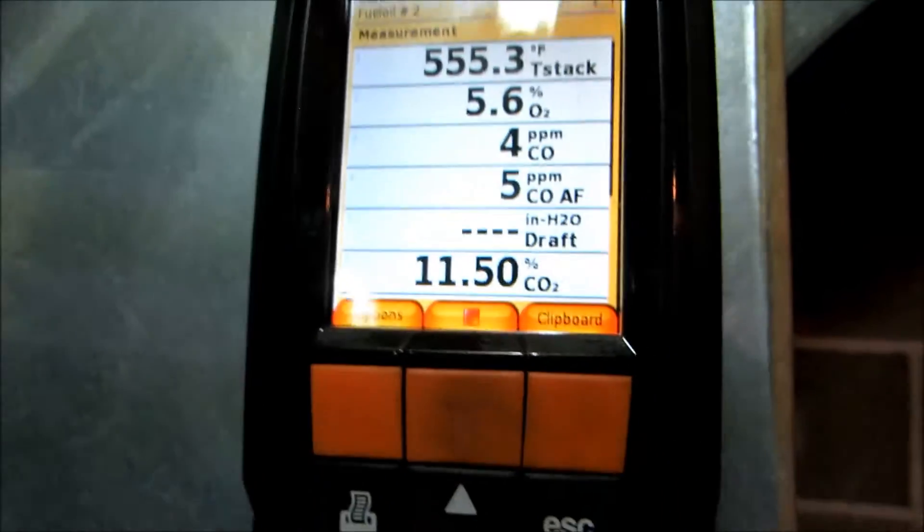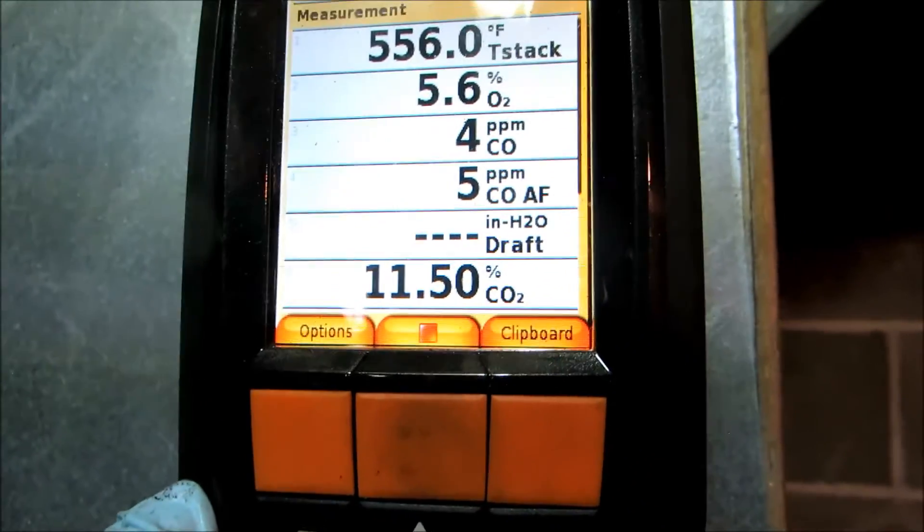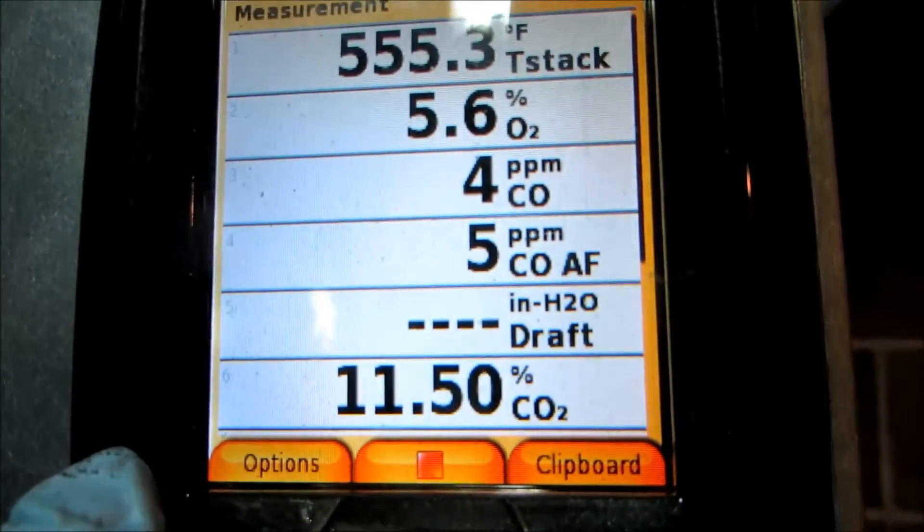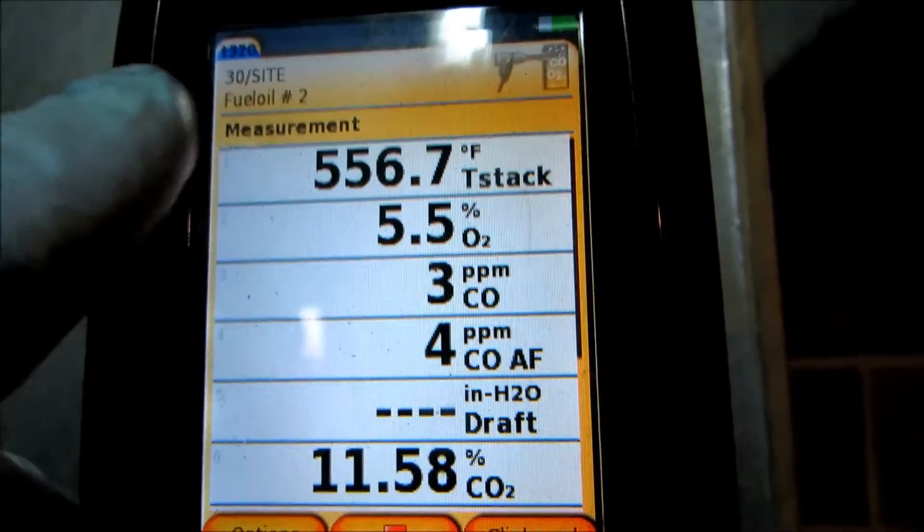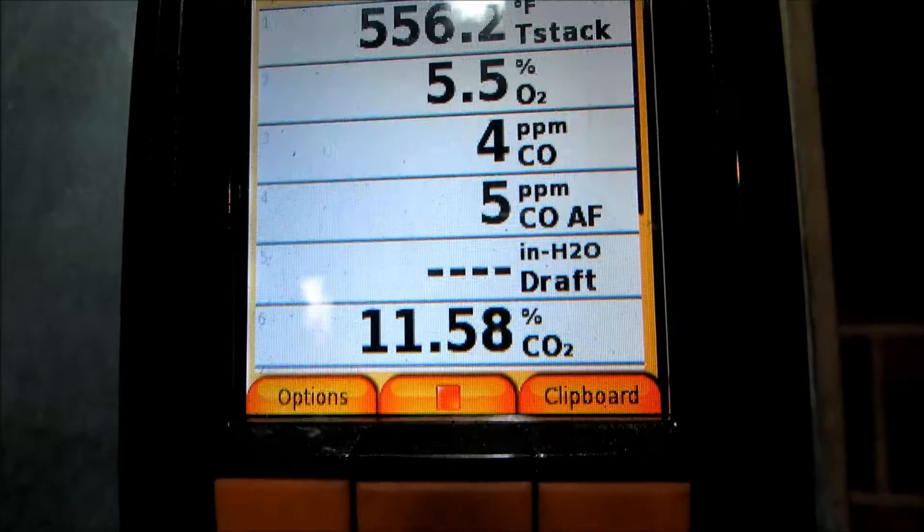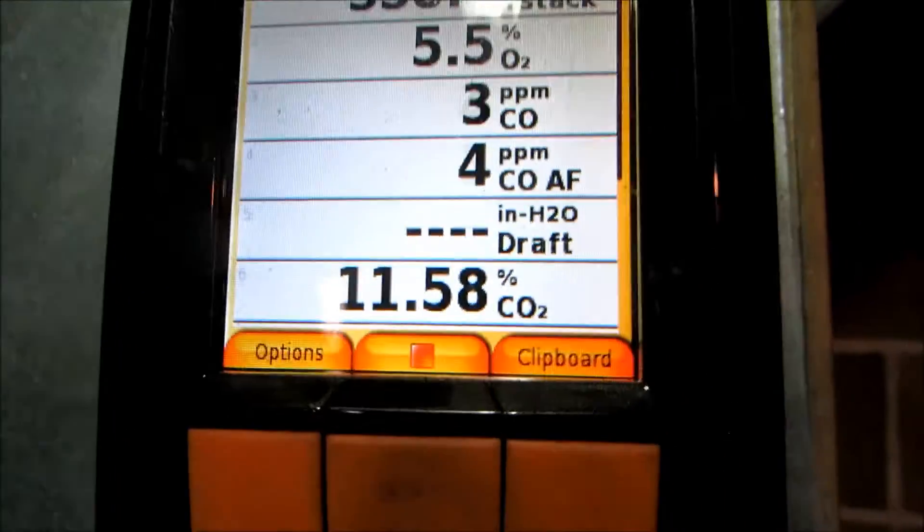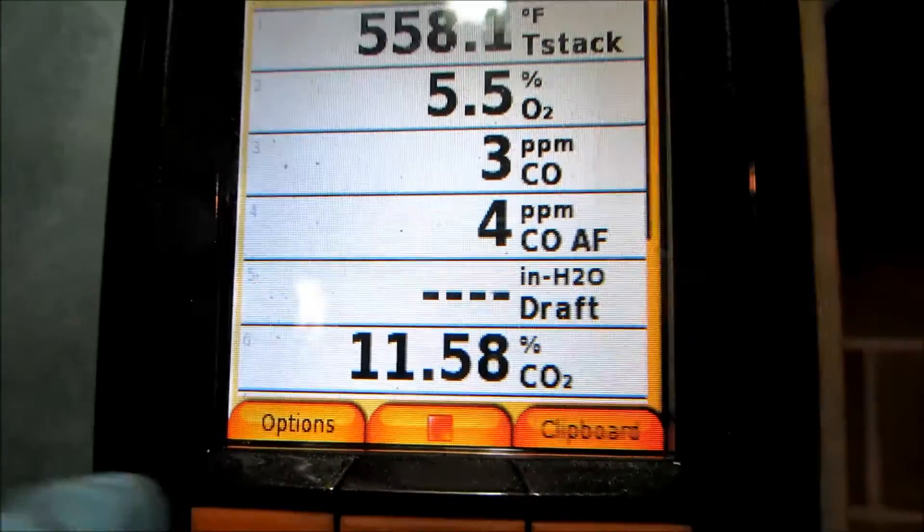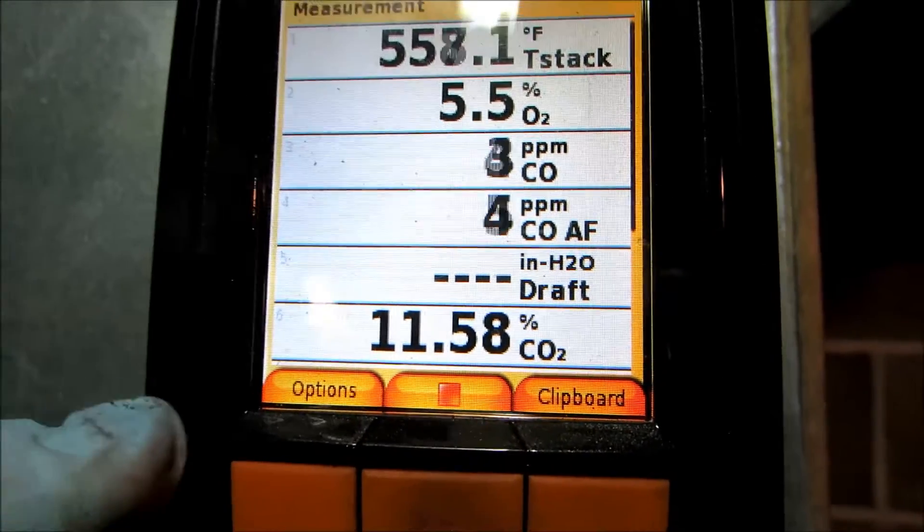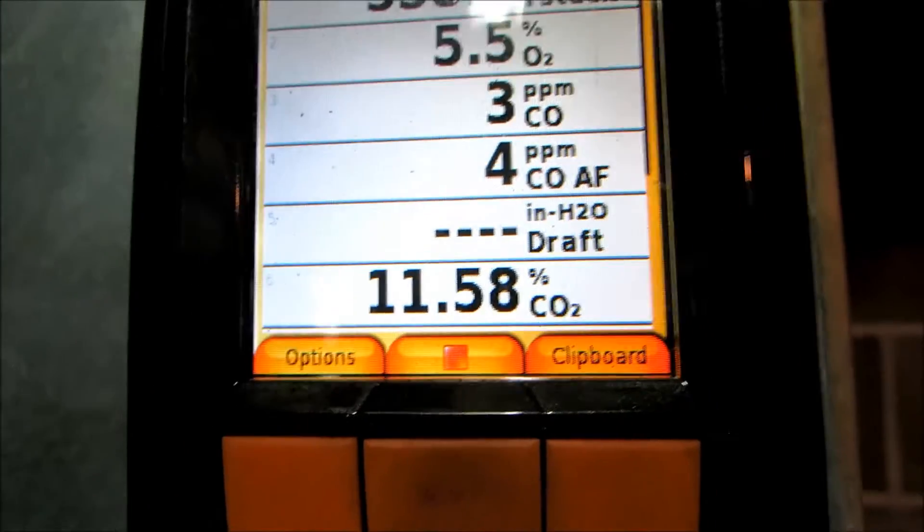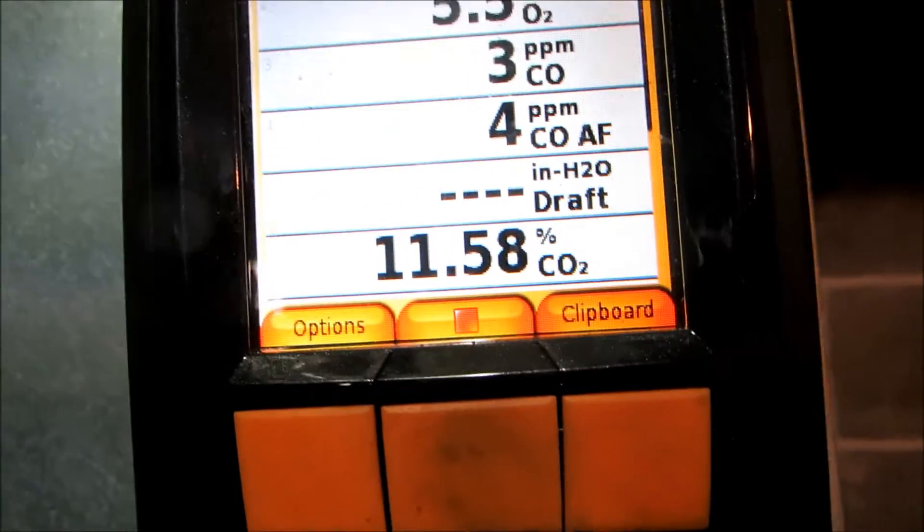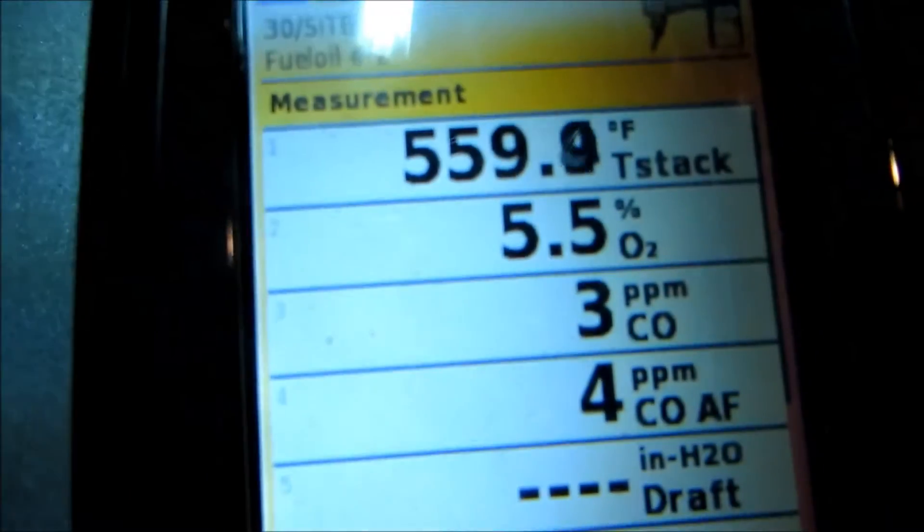We'll see what we're seeing over there. The value of the efficiency is the CO2 and the stack temperature - that'll give you efficiency of the unit. The higher the CO2, the better off you are, but you don't want to go too high because now you're going to be producing smoke. See, the parts per million really hasn't changed there.